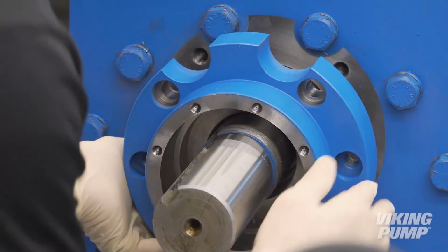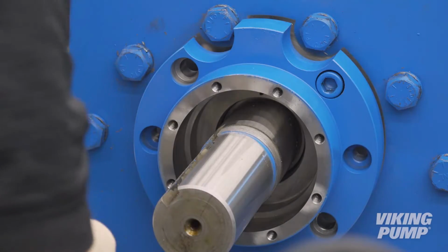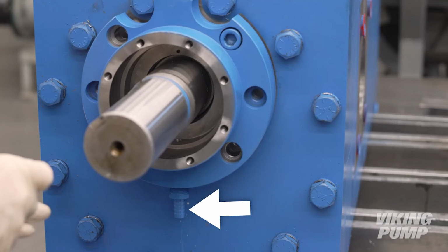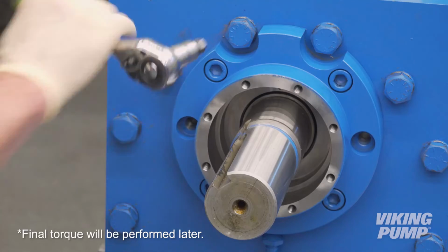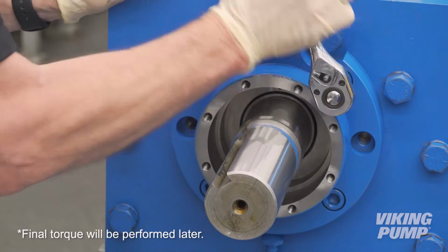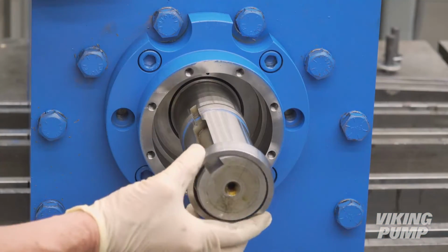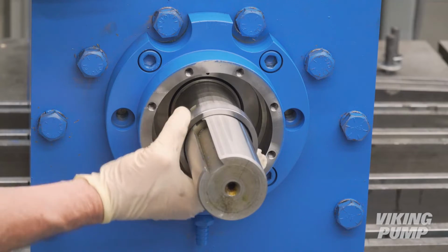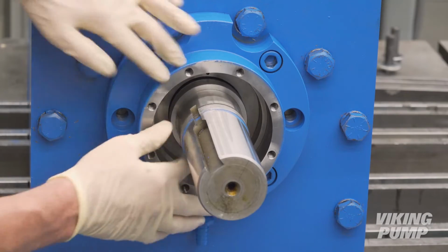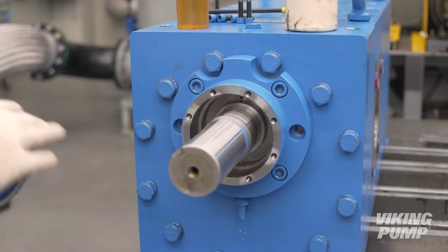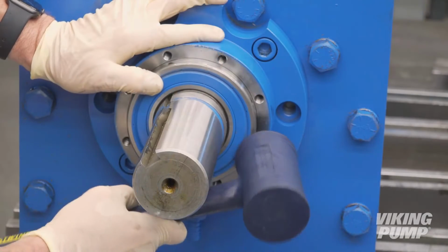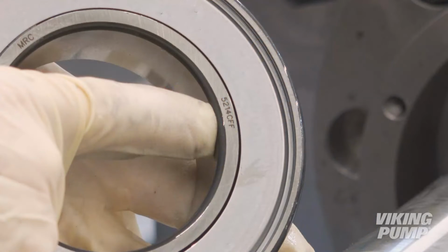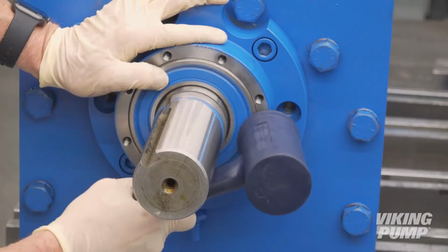You may use the seal holder to fully set the seal. Install the seal holder assembly with the seal housing drain in the 6 o'clock position and tighten the cap screws in a star pattern. Next, install the inner bearing spacer. Coat the thrust bearing in light oil and install onto the shaft. Make sure the printed letters on the outer race of the bearing are facing outward.